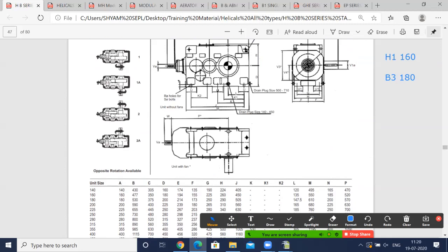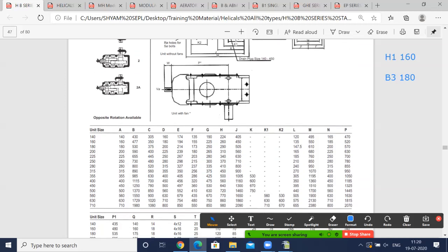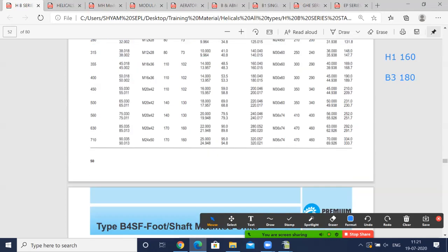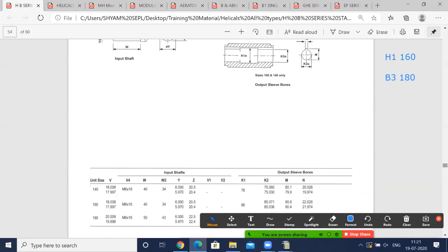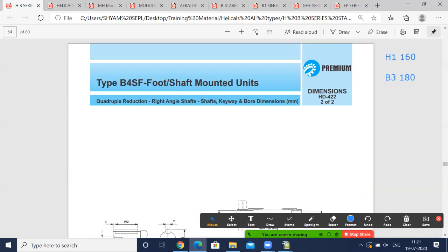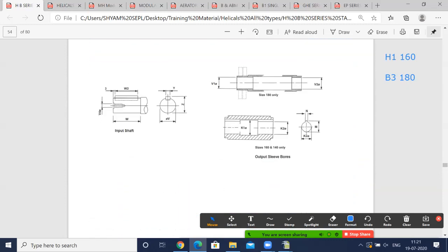Now another key here is the center height. The center height of any helical gearbox designed in this catalog is basically one size higher than the model. So if the model is B3 180, the center height of that model will be 200. 180 will be 200. Okay, so model to model, center distance, center height. This is how the naming came about from 140 to 710. Now let me show you what that hold back thing is. Even the bell housing page is also available. And as you can see in these SF parts, wherever the output is hollow, there is an option of shrink disk. Now what a shrink disk is, this dotted part, I'll also explain.